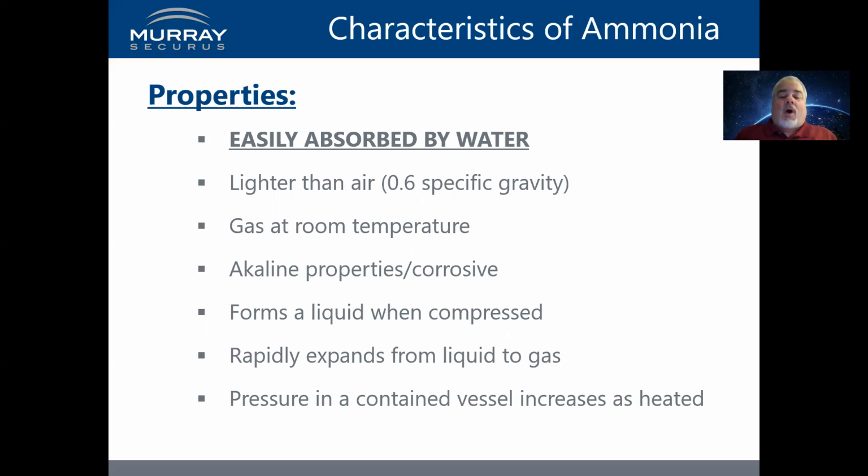Easily absorbed by water or easily reacts with water. It is a lighter than air material when it's a gas, so it has a specific gravity of 0.6. And because it's lighter than air, it will rise up in the atmosphere, but it depends on the room and the temperature. It can come out of a unit and be concentrated near the floor temporarily. Eventually it will rise up, but you can't count on that.